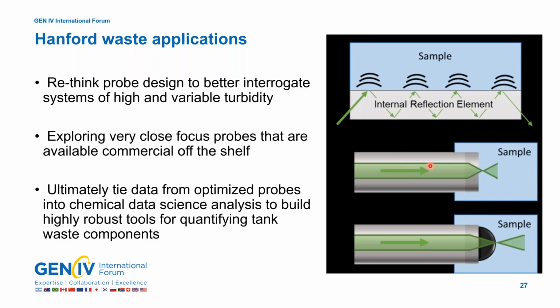They have either a close focus design. So this is laser light coming through our probe, and we have an optical window where we focus the laser beam right at the interface between our probe window and the solution sample. Instead of sending the beam way out in the sample where it has scattering from some of the solids in solution, we have it right against the edge, so we have minimized the scattering from the particles in solution.